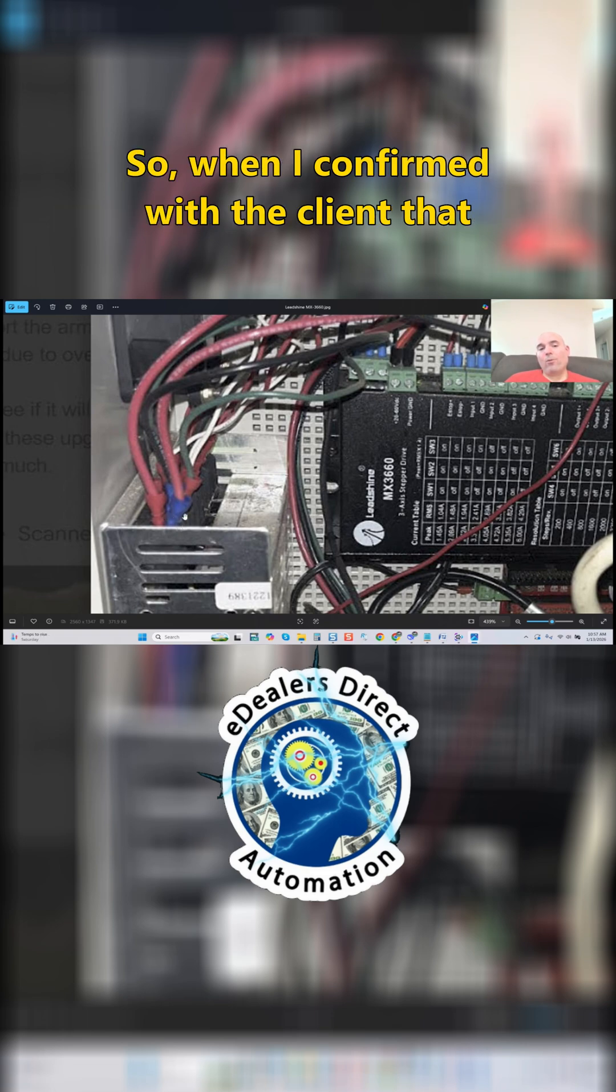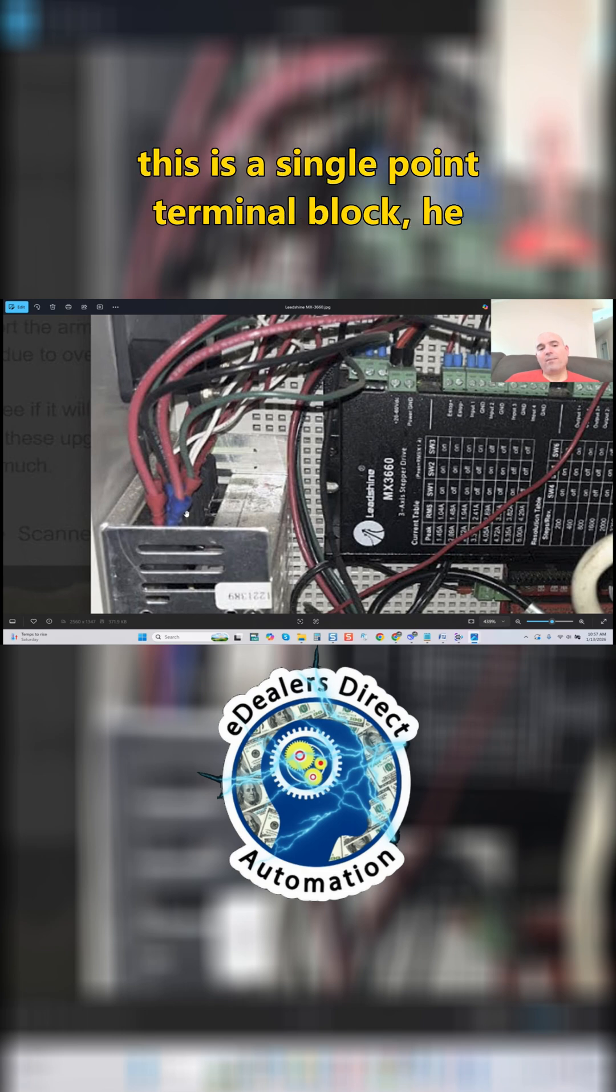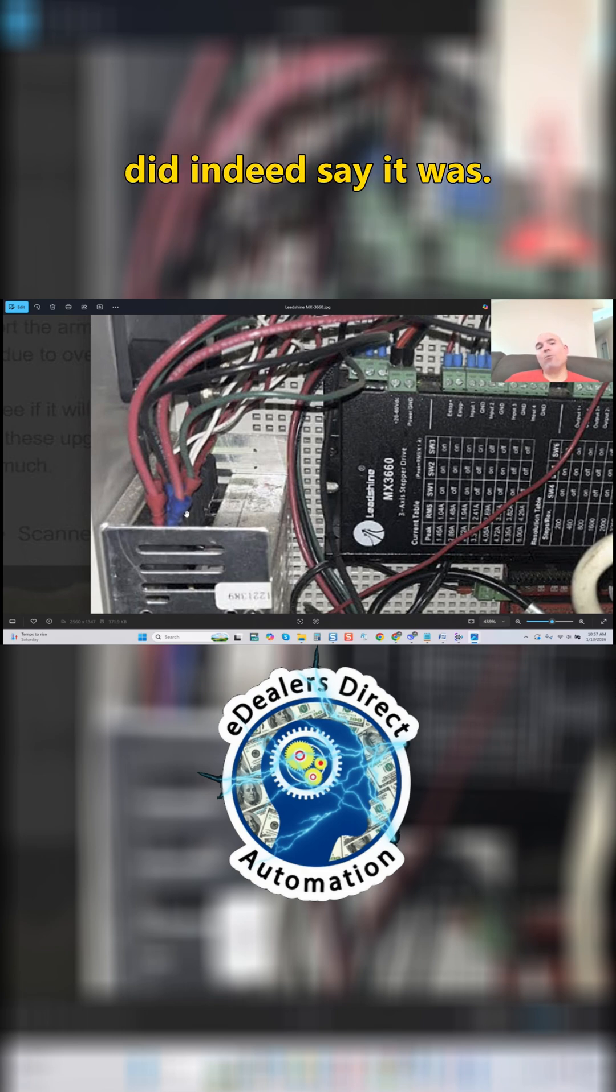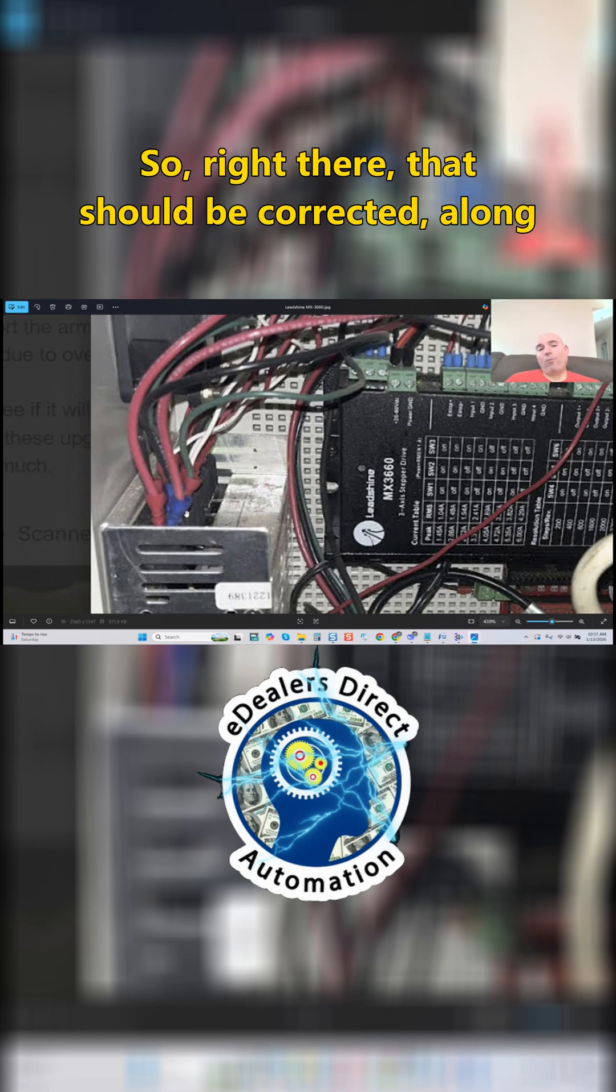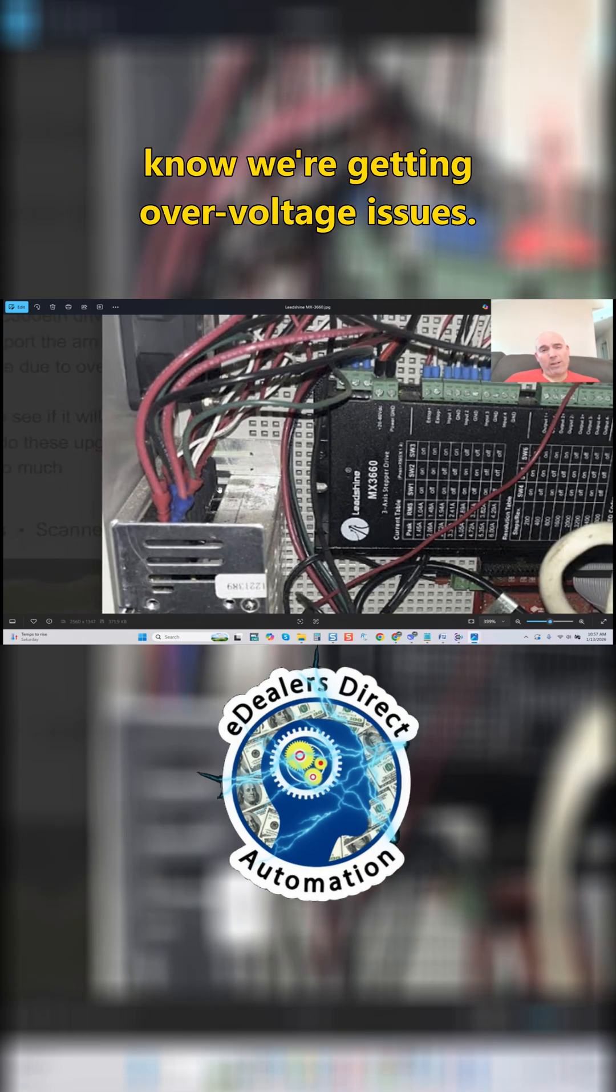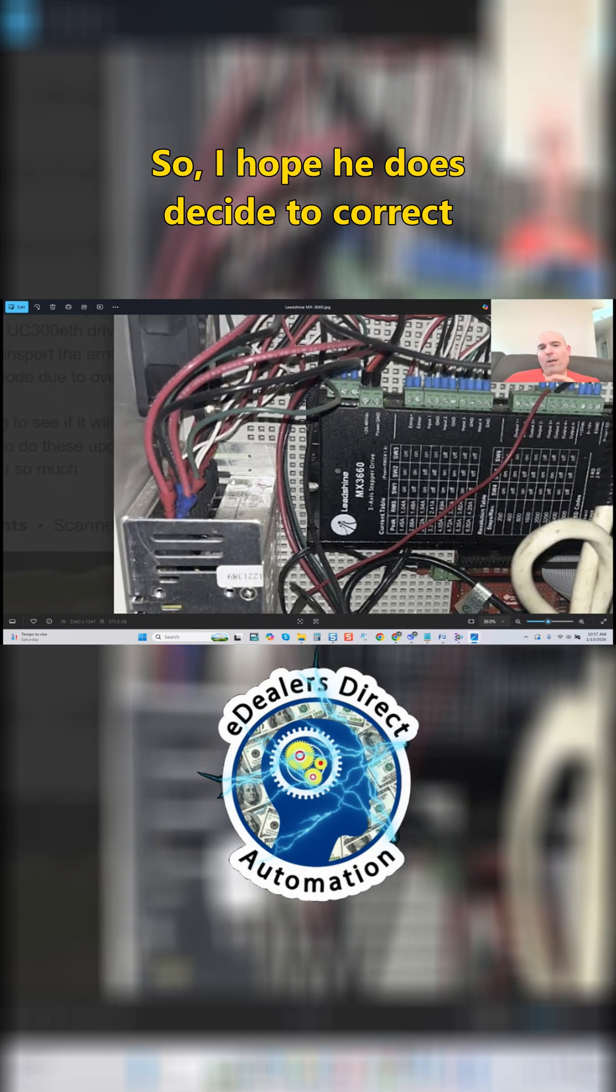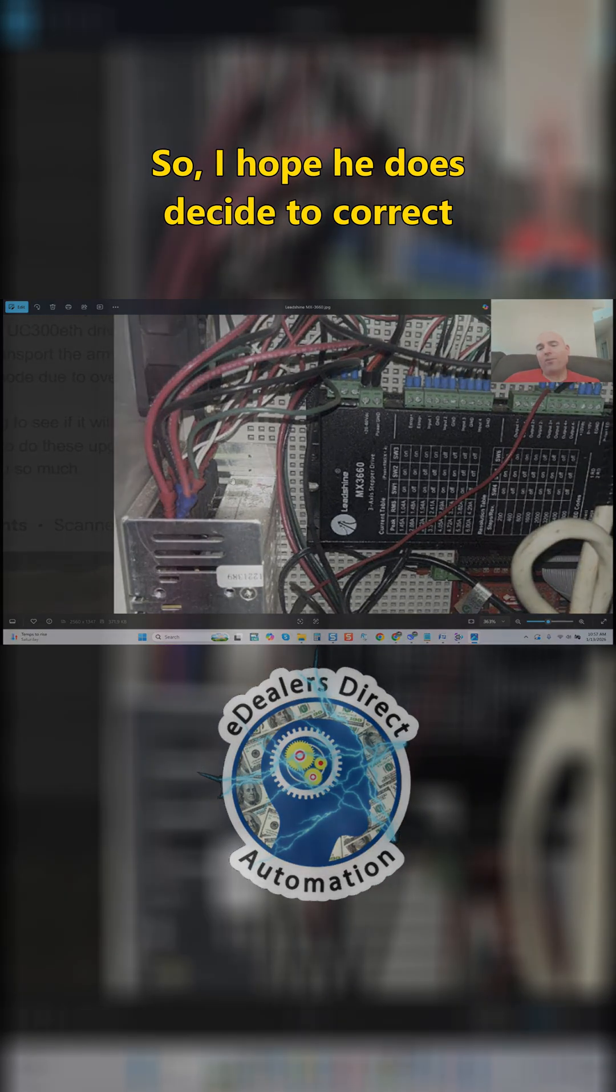When I confirm with the client that this is a single-point terminal block, he did indeed say it was. So right there, that should be corrected along with the crimp connections, especially when we already know we're getting over-voltage issues. I hope he does decide to correct that.